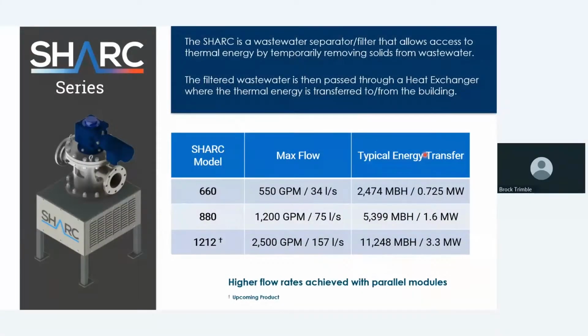And with that, let's jump into the SHARC series. So the SHARC operates differently than the Piranha. The SHARC unit that you see here is our proprietary piece, and this itself is a wastewater filter. So this unit allows access to thermal energy by temporarily removing solids from the wastewater stream that's pumped through this unit. We send the solids back to the sewer, and we use all of that really powerful filtered wastewater to run through a downstream heat exchanger where we move energy to or from a building.